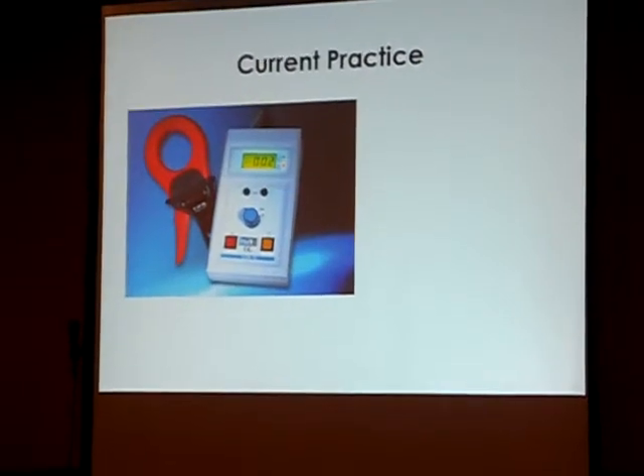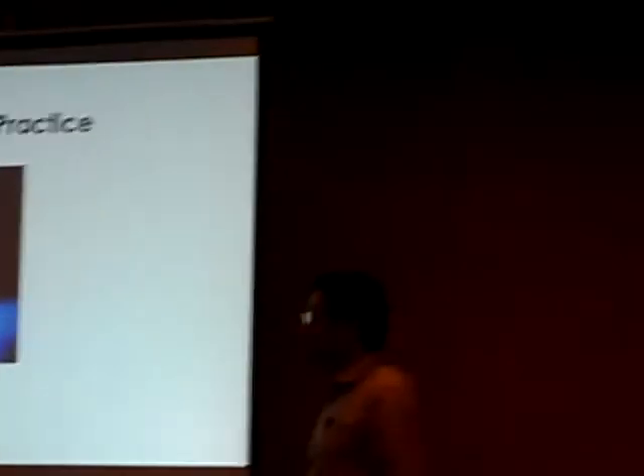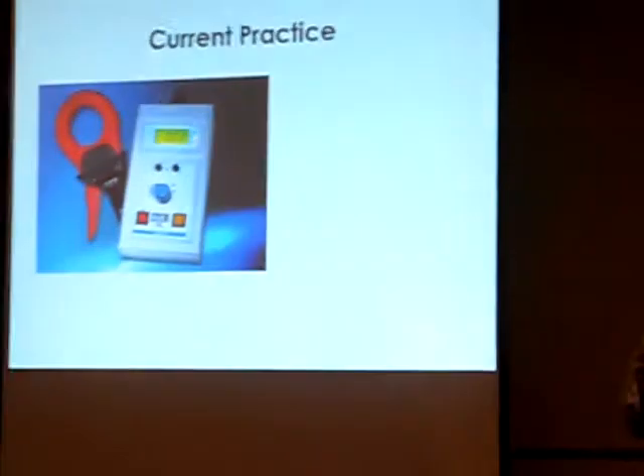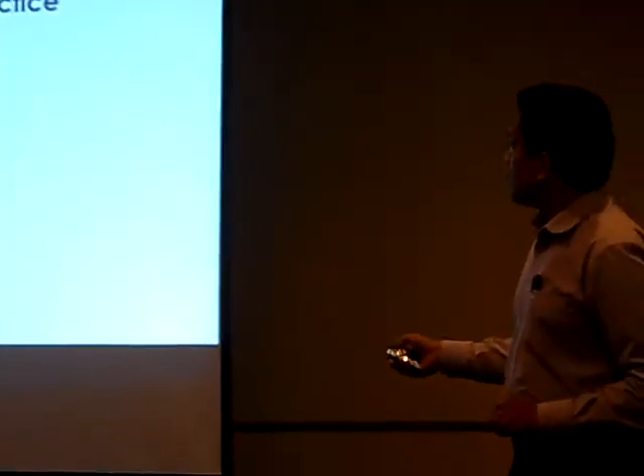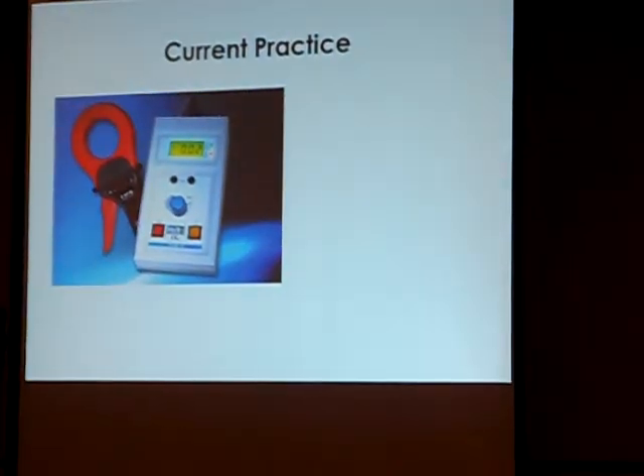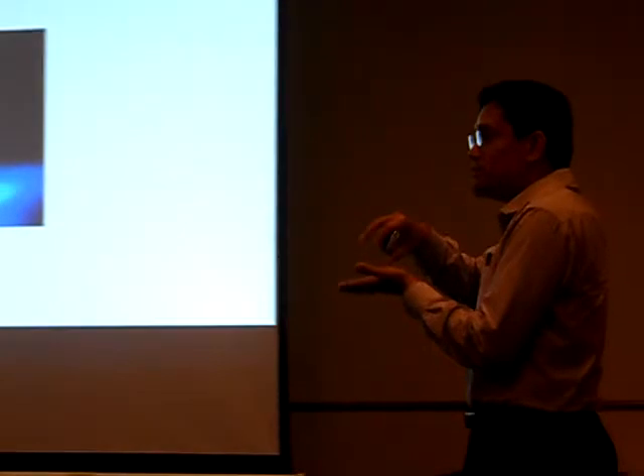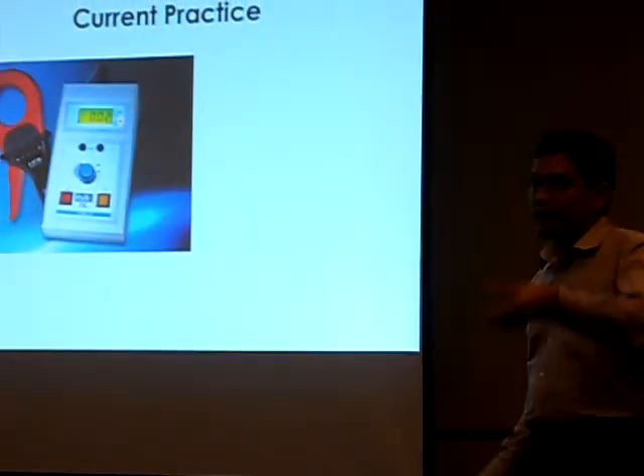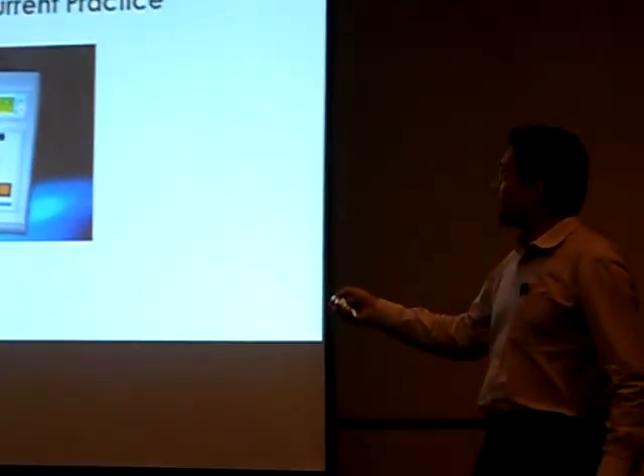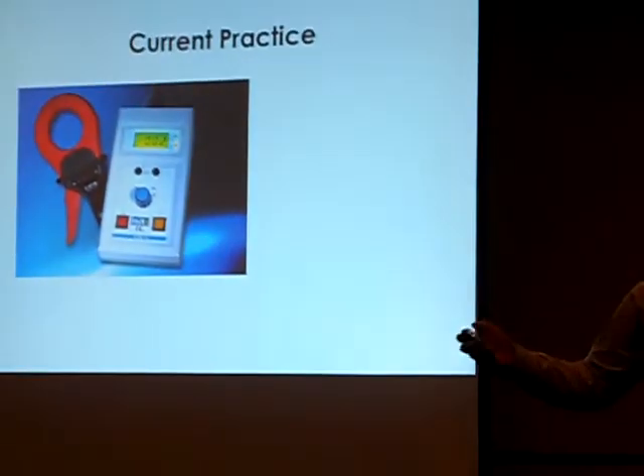Let me show you how utilities in Malaysia do this. They use equipment called SCAR-10 with a clamp meter to measure leakage current. The technology and circuitry is inside, and all they get is a meter reading or digital display with maybe 3 functions: leakage current, temperature, third harmonics, whatever.